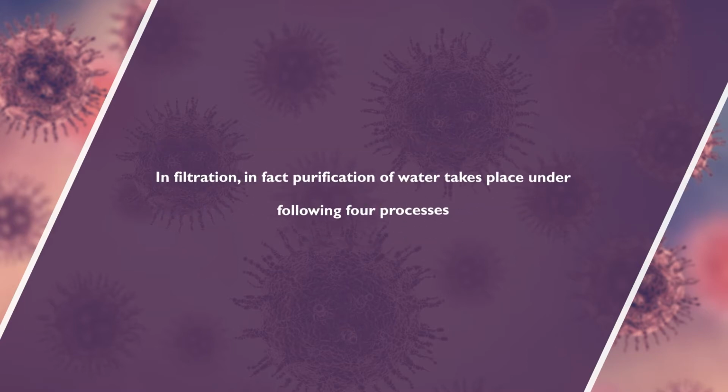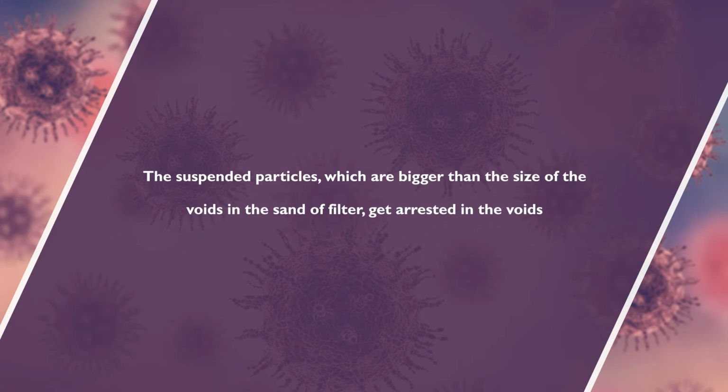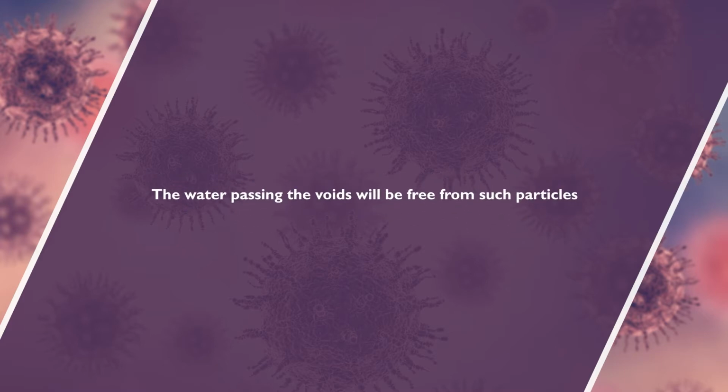In filtration, purification of water takes place under four processes. First, mechanical straining: the suspended particles which are bigger than the size of the voids in the sand of the filter get arrested in the voids. The water passing through the voids will be free from such particles.